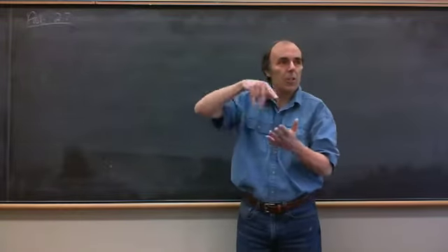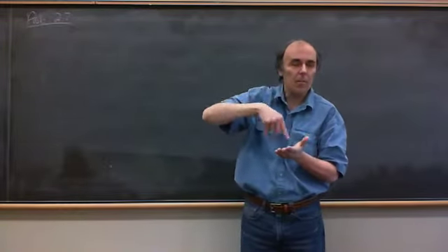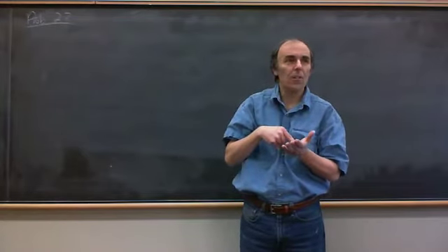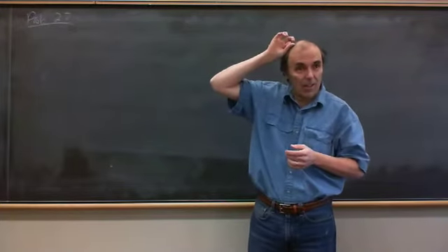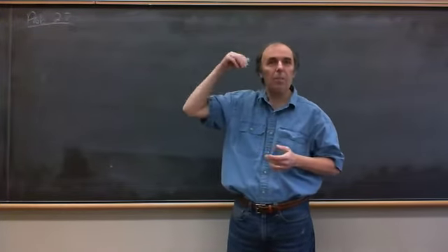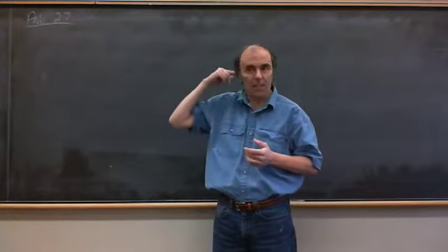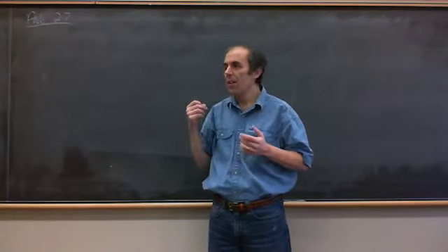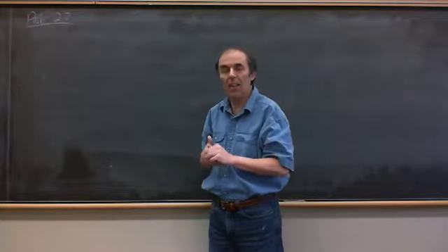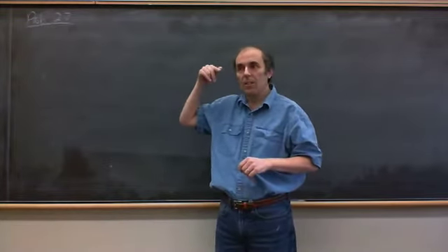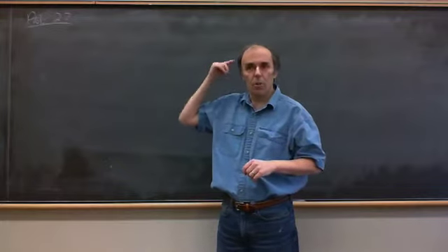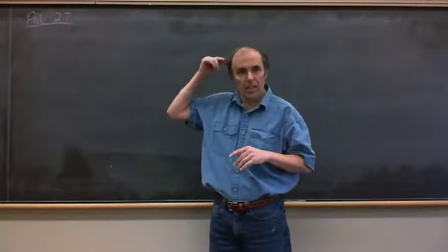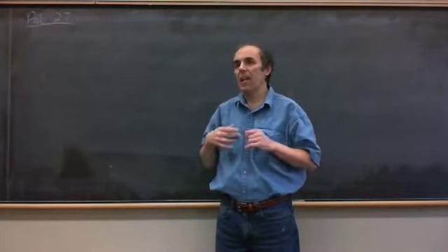Well, they're inducing electrical currents by Faraday's law of induction in the electrode. The electrode is usually a silver electrode. Its electrical conductivity is maybe 10 million times higher than the electrical conductivity in the scalp, skull or brain. Therefore, you get much larger electrical currents flowing, and a lot more joule heating. Joule heating is negligible in the body during this, but joule heating in the electrode can actually be significant.